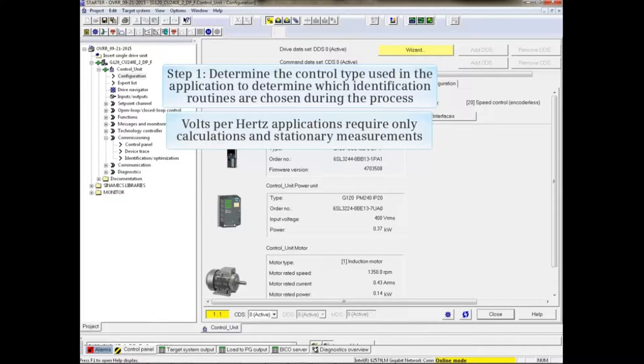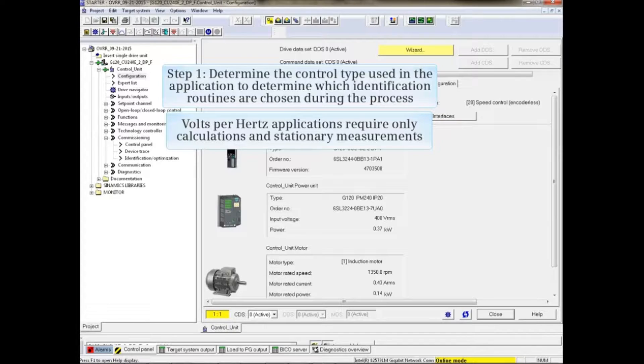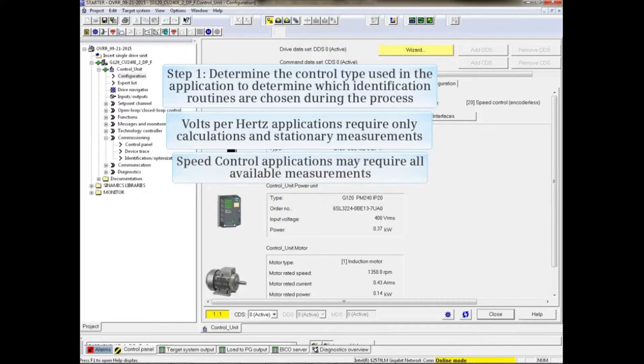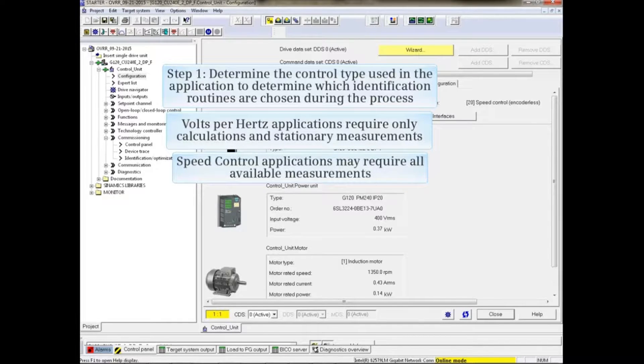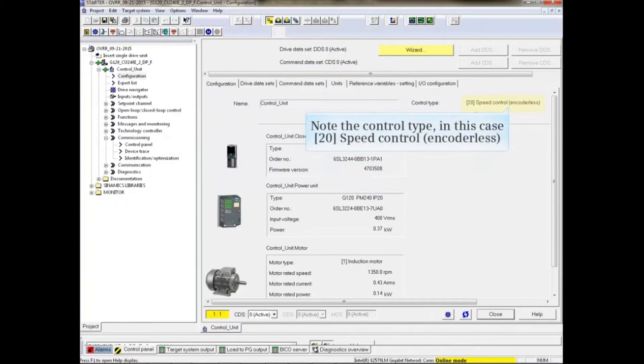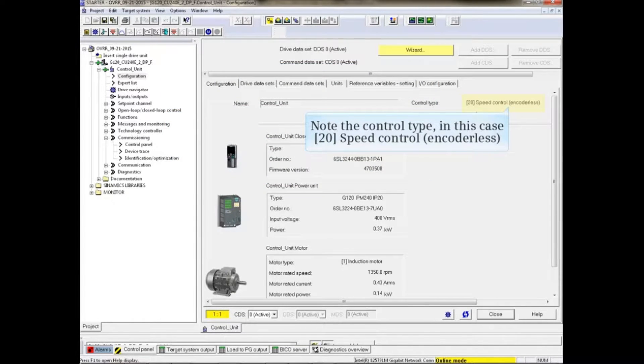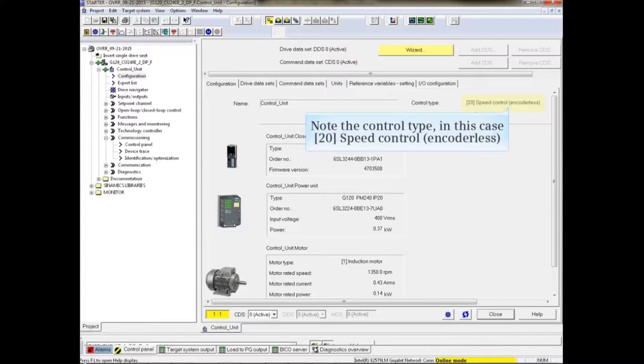Volts per hertz applications require only calculations and stationary measurements, while speed control applications may require all available measurements to be done. In this example, we have speed control encoderless as shown in the control unit configuration screen.